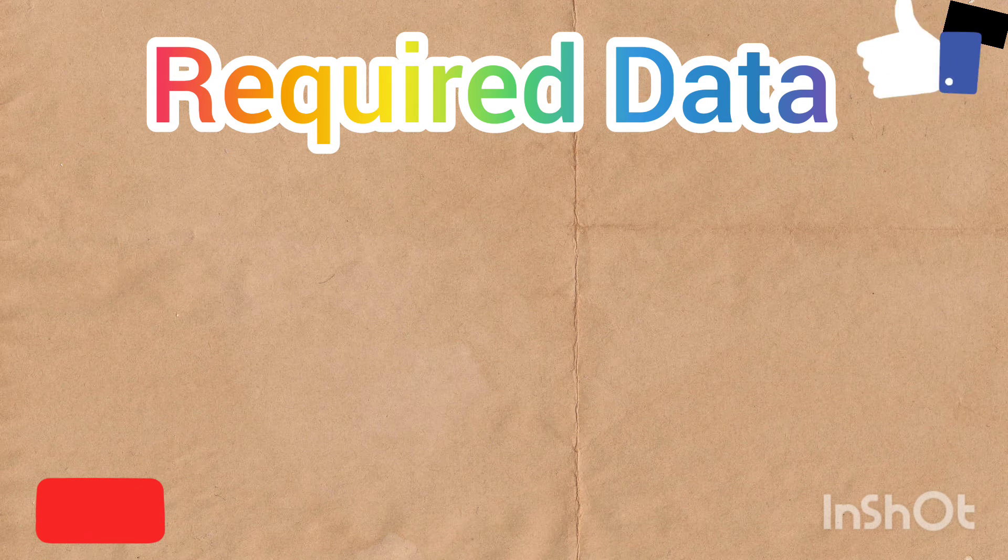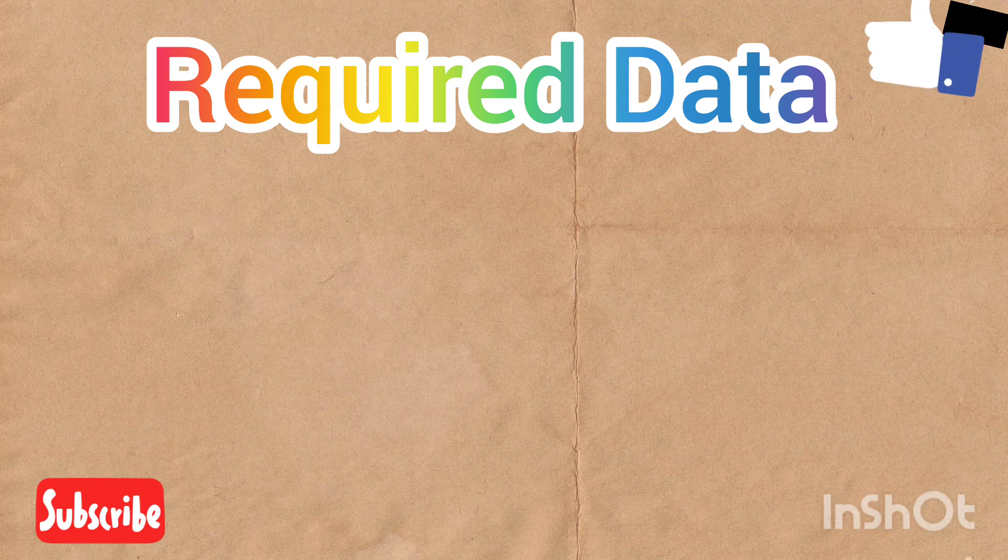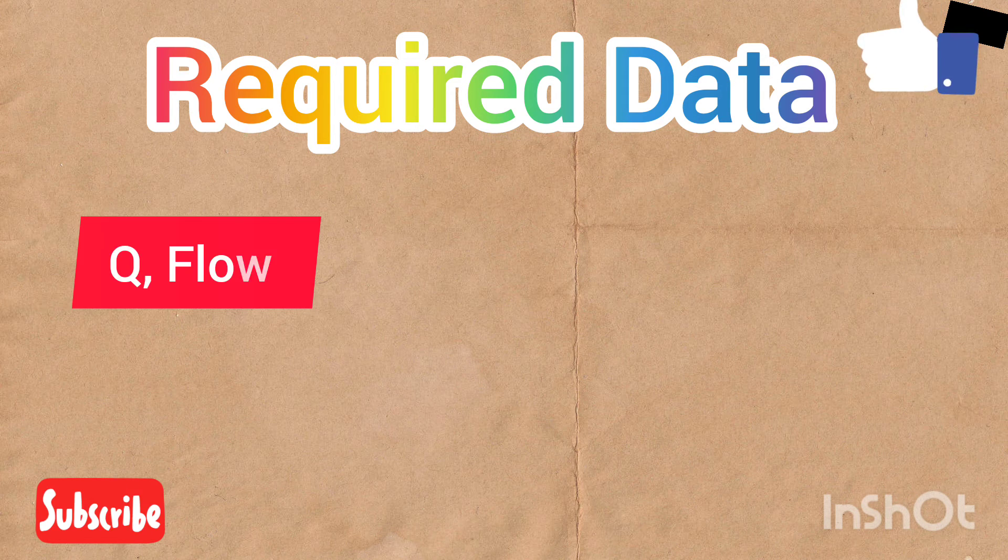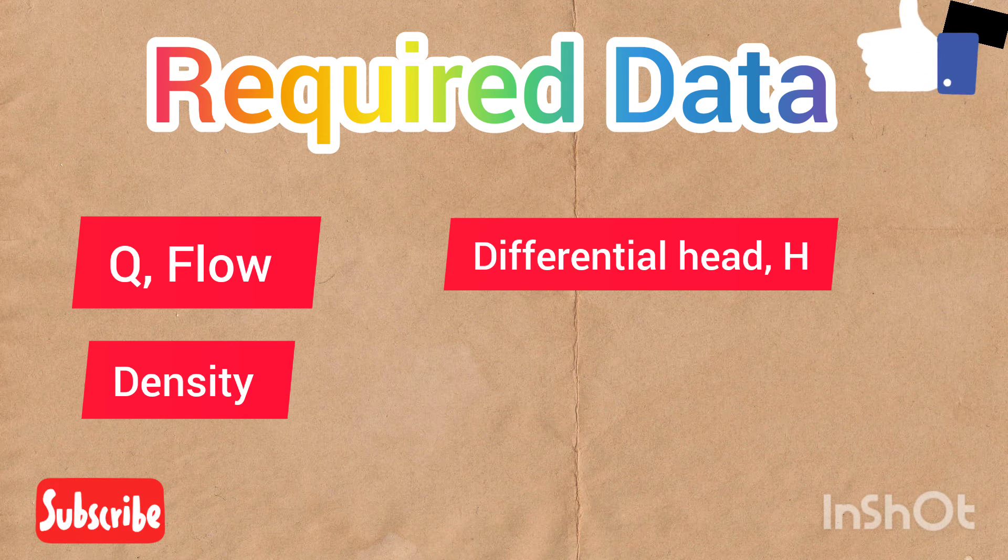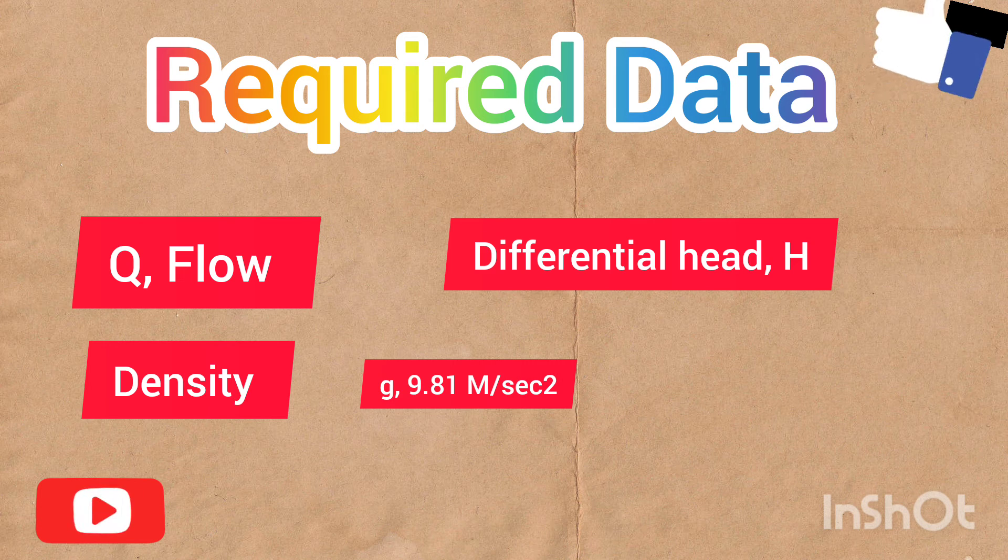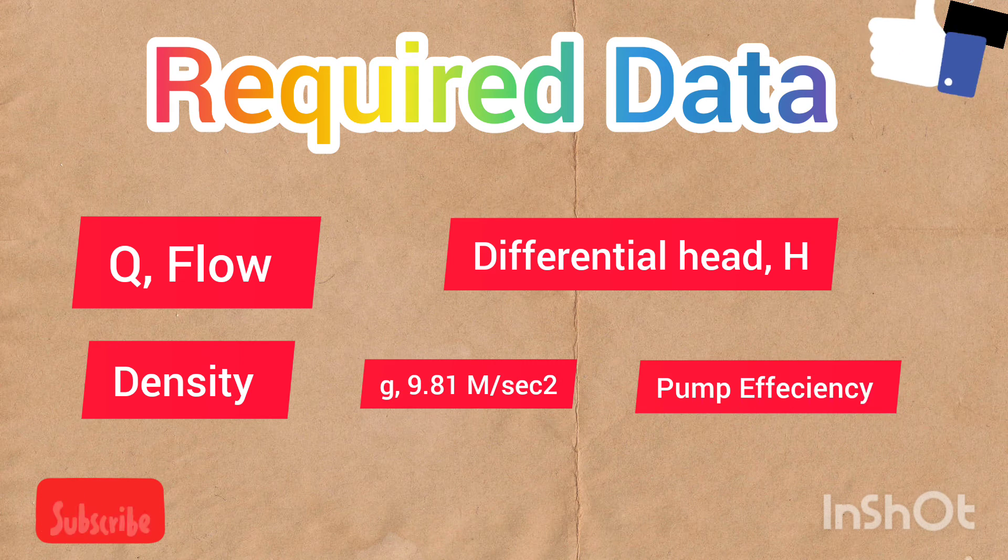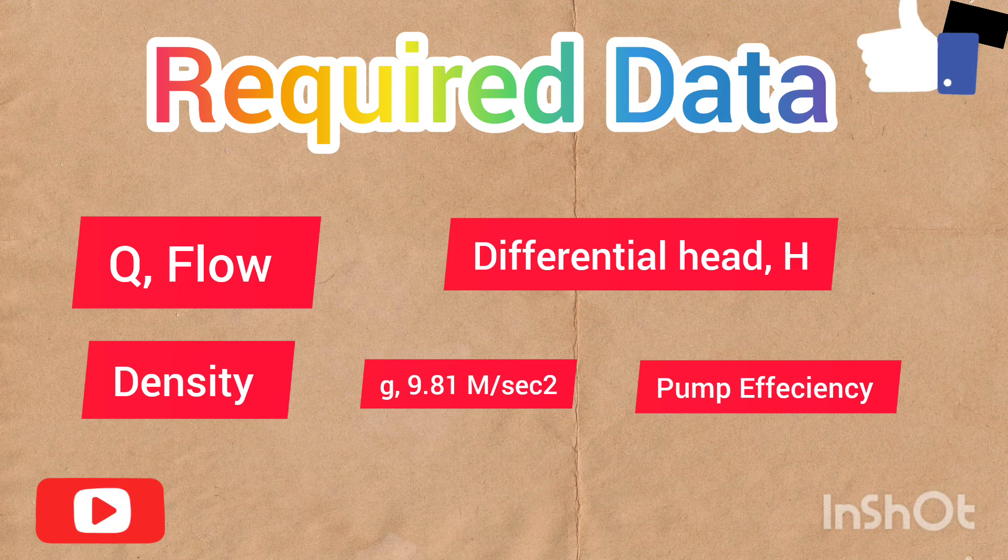Let's discuss the data which is very important to calculate the power required for a centrifugal pump. We need flow rate in meter cube per second, differential head in meter, density in kg per meter cube, the g value which is 9.81 meter per second squared, and pump efficiency.